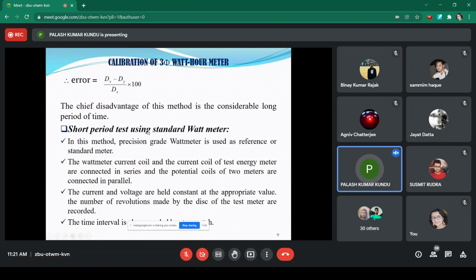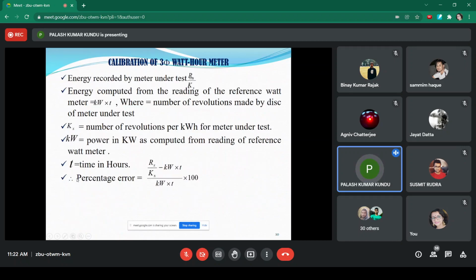Our laboratory method uses the third method, that is, the short period test using the standard wattmeter. That means whenever the calibration experiment is performed, the reading obtained by the test meter should be compared with the standard meter. Here, instead of using a standard energy meter, we use the standard wattmeter, because we know electrodynamic type wattmeters are considered to be the standard meter in all types of calibration experiments. That may be the calibration of wattmeters or of energy meters. So the short time test using a standard meter is our case. And the formula to find the percentage error is given by this formula. It is easier to follow.